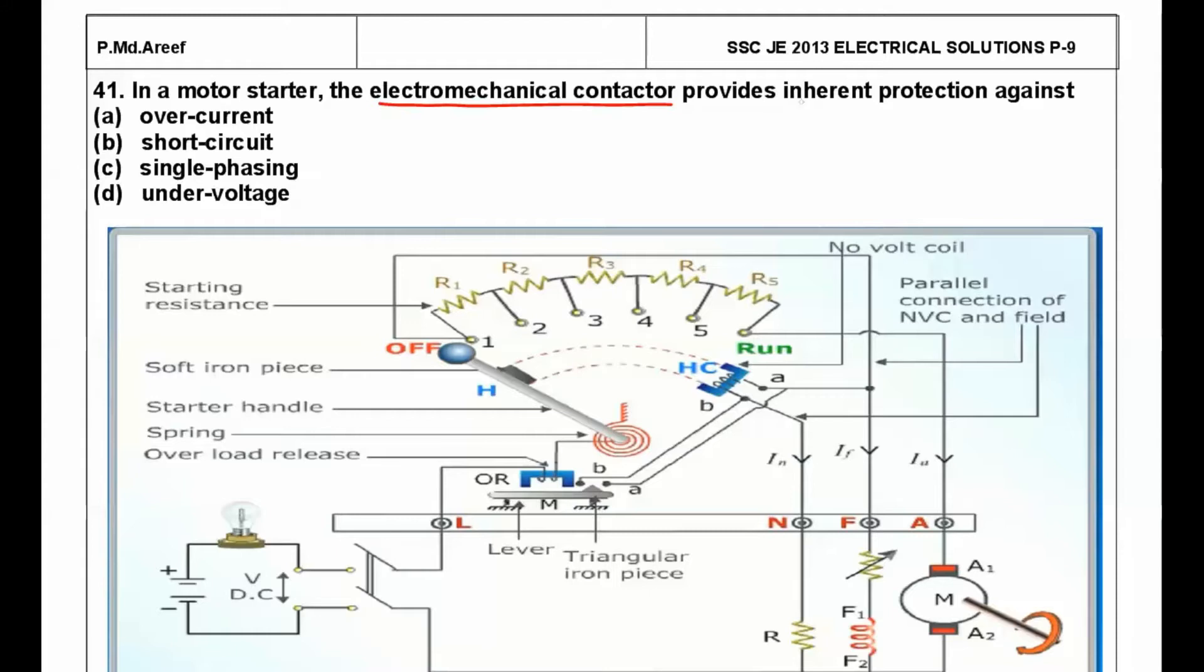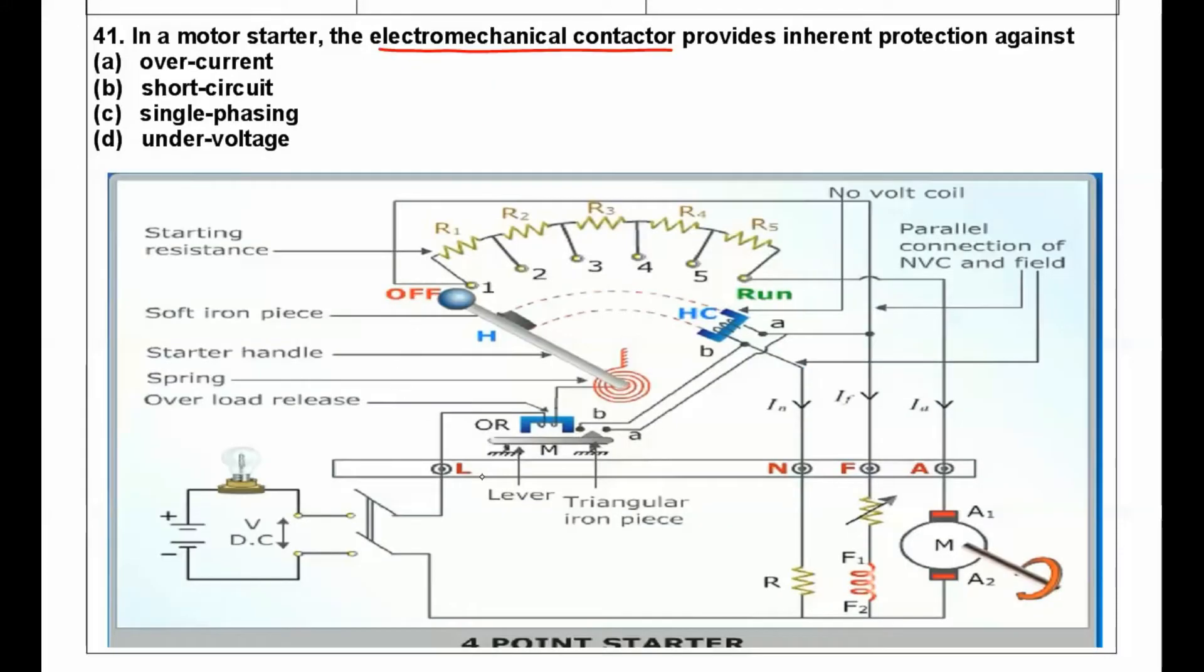As you can see here, it's a four-point starter and this is an electromechanical contactor. Here we have a holding coil, so whenever the voltage is below the rated voltage, the holding coil releases this contactor spindle or moving contact.